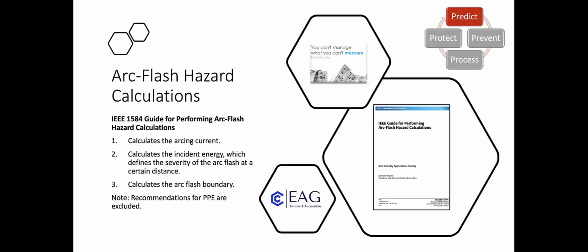Firstly, the IEEE guide, if we just go down the list on the left-hand side, it allows you to calculate the arcing current, which is very important if you wish to design out the hazard on electrical equipment. Now, right at the end of this presentation today, I've put a special slide in for all you design engineers out there, because I'm going to just talk a little while about designing around arcing current. So if you forget everything else that I'm going to talk about today, arcing current is quite important, because that's what your protection has got to protect against if it's going to quickly disconnect an arcing fault. And I'll share that with you later.